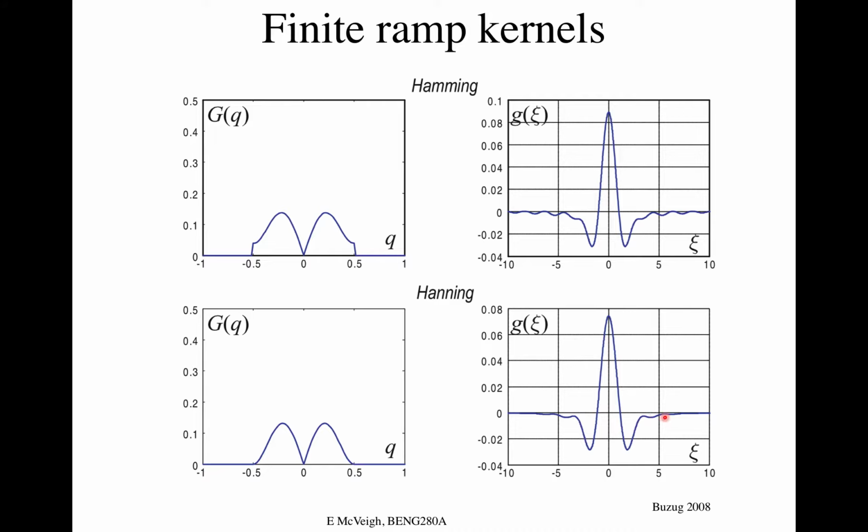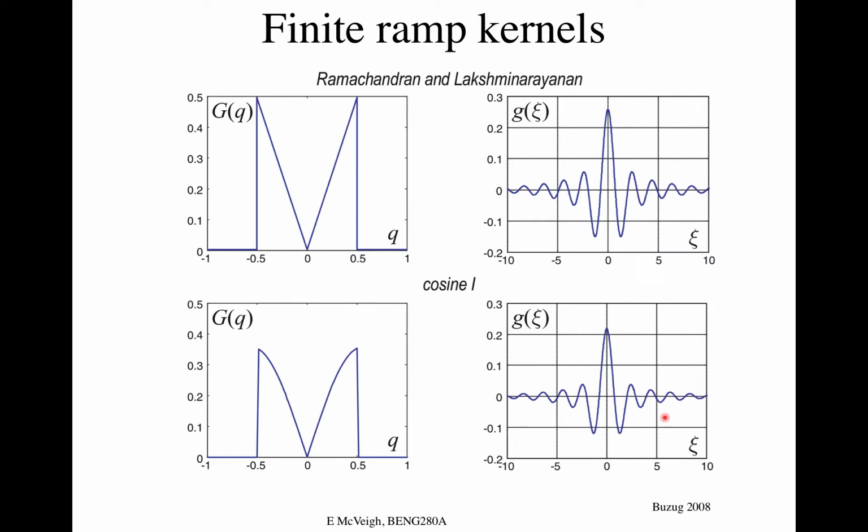What are the trade-offs between, say, Hanning and a ramp? So if you want to really find something that's tiny in your picture, and you're willing to make a call on things that are single pixel intensities, then you want to use a Ram-Lak filter and pull out all of the high frequency stuff, but you're going to see really high frequency noise, so it looks like a really hashy picture.